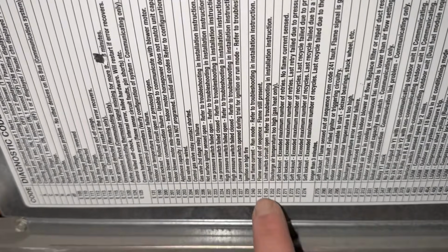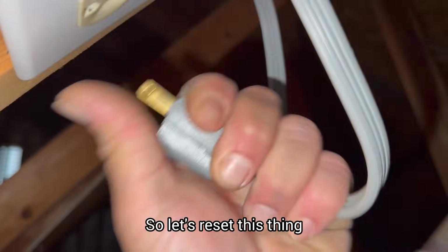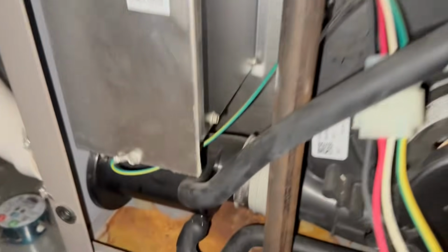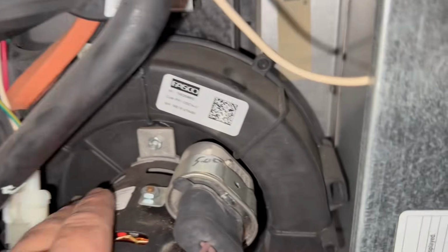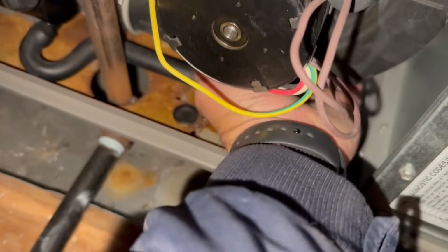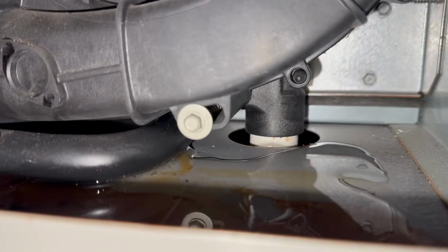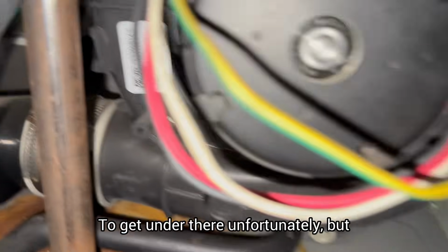So E274. E274 and E250. E250, limit switch circuit open. E274, soft lockout. So we're in a soft lockout right now. So let's reset this thing. Limit switch was open, but something's leaking. I'm probably gonna have to take the motor off to get under there, unfortunately, but let's reset it, see what it does.